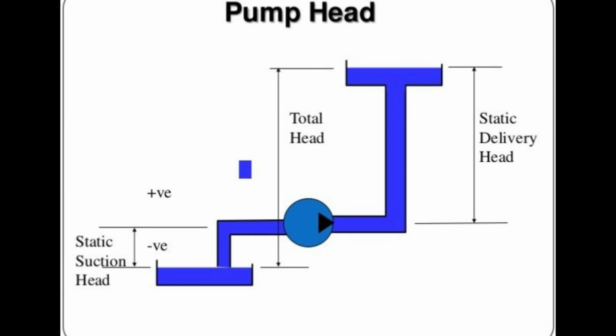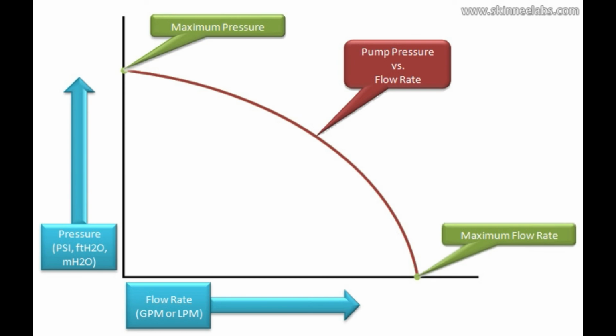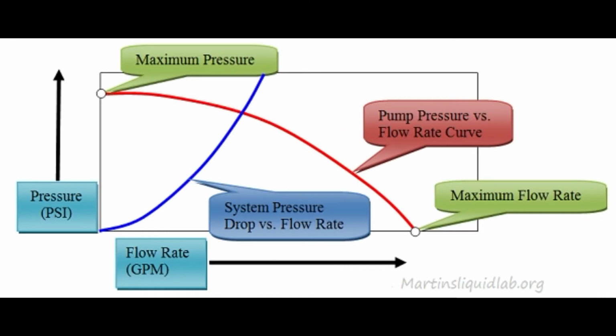7. Flow rate and pressure. Your total volume and knowing how much time you have to move the fluid will determine flow rate. Pump differential pressure can be calculated by knowing pipe size, length and fittings, static lifts, and system equipment, filters, valves, etc.